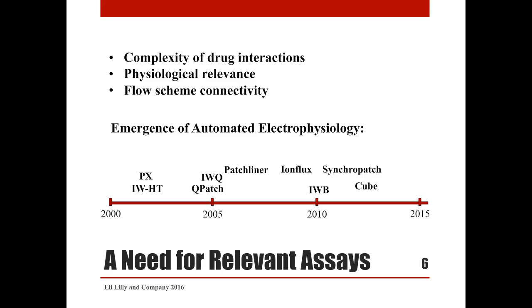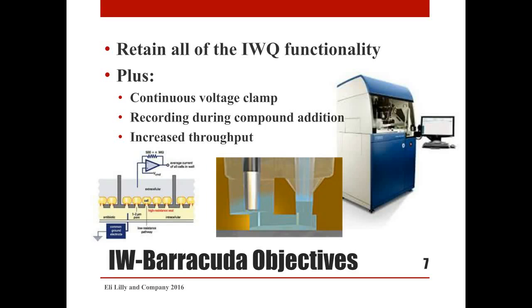Electrophysiology, with its ability to control membrane potential and its direct readout at millisecond temporal resolution, is often the most suitable technique. However, the low throughput of manual patch is not adequate for industrial drug discovery. Automated electrophysiology instruments can be divided into gigaseal instruments capable of high-fidelity voltage clamp, and sub-gigaseal instruments with the advantage of higher success rate. This talk will focus on IonWorks Barracuda, which was introduced five years ago and follows IonWorks HT and IonWorks Quattro in the line of sub-gigaseal instruments.